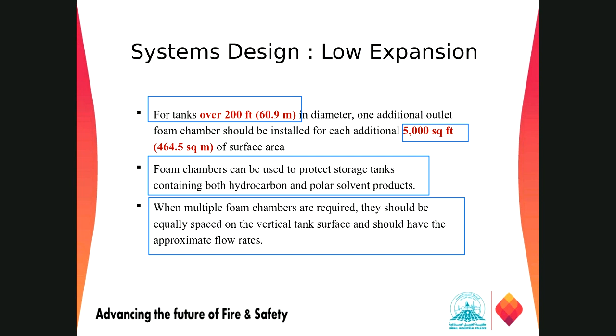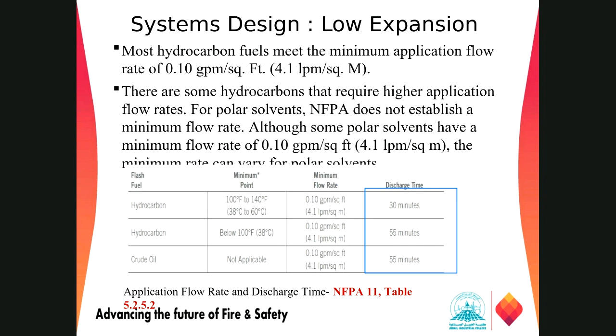And here we have the flow rate and discharge time, right? For low expansion foam, most hydrocarbon fuels meet an application rate of around 0.10 GPM per square foot. As per NFPA, for a hydrocarbon with a flash point between 38 degrees Celsius and 60 degrees Celsius, we need 0.10 for 30 minutes. If it is below 38 degrees Celsius, we need 55 minutes. And if it goes further down, the time duration is based on the type of product: if it is crude oil, what is the flash point, what is the boiling point. Based on that, we have to take care of these things.